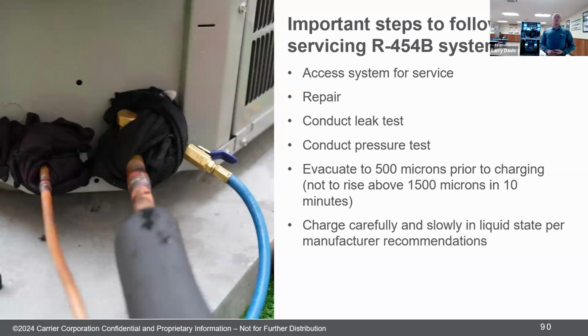Okay. So again, when you're doing a repair, after you've done the double evacuation and made your repair, you're going to do a leak test with nitrogen. You're going to evacuate it, and then you're going to charge it just like before. The big thing is when you're opening that system up, the double evacuation with the purges with nitrogen in between is to make sure you get any pockets of residual refrigerant out of that system.